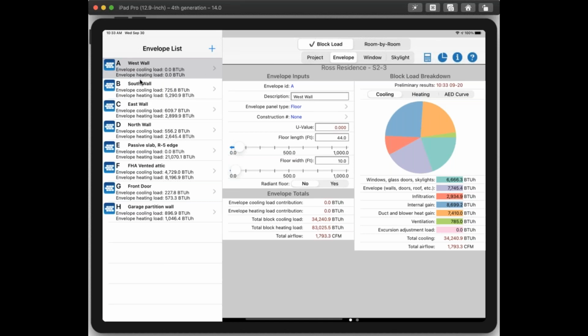So here I've predefined a bunch of envelopes. One more thing - I get this question literally every week: do I need to model my internal walls, say between my living room and dining room? No, you do not, you can totally ignore those walls. The reason is there's no heat transfer across them - most of the time you'll have the same cooling set point in your living room as in your dining room, so there's no need to model that wall. It adds nothing to the loads. Make sure you don't worry about internal walls other than partitions.